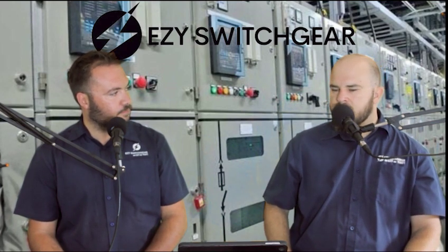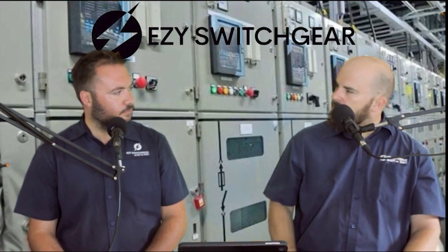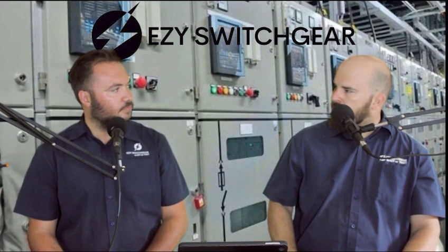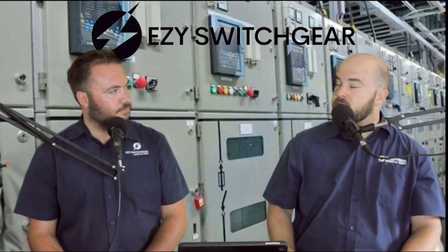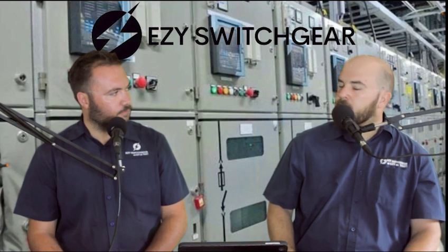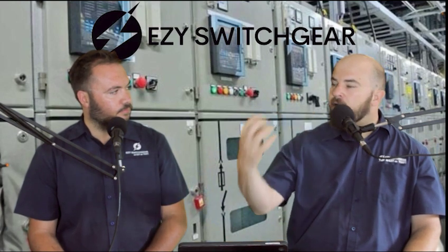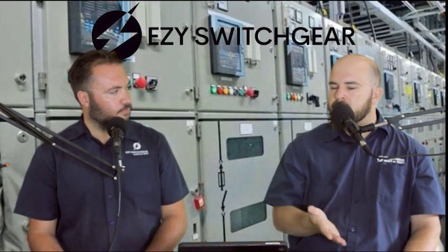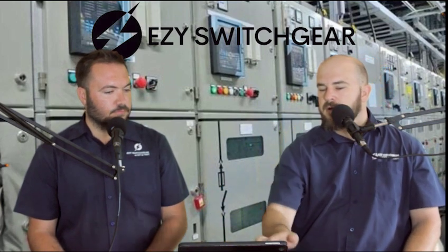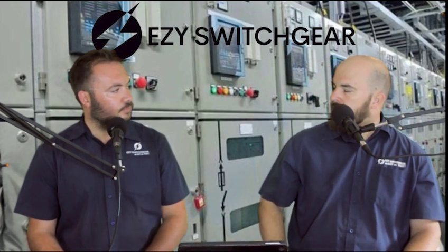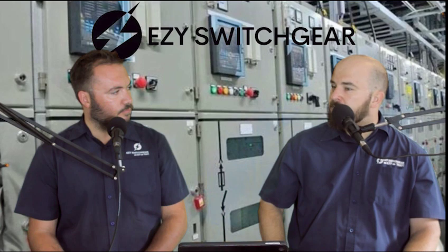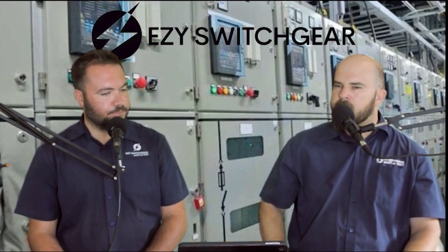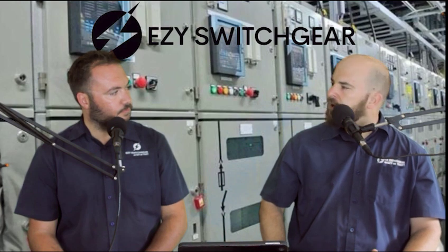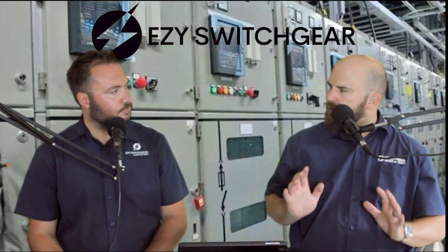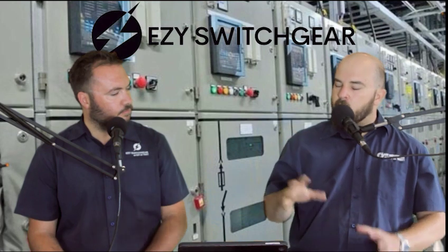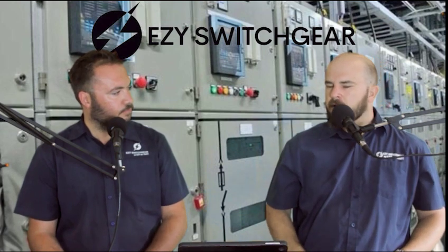Yeah. So in countries like South Africa, where maintenance is not always the highest, it's not always on every menu, oil insulated switchgear is just a hazard, it's a fireball waiting to happen. So you will find a lot of guys going away from oil insulated switchgear to gas insulated or air insulated switchgear, so that they can mitigate that big risk. But through the years, oil switchgear has been the staple of the world. Yes. I think that since the late 90s, the other types of switchgear became super prominent, and oil switchgear and oil circuit breakers and all of that was pushed to the side.